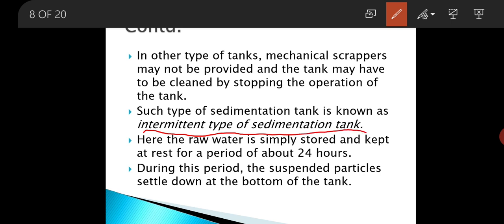One is continuous flow type sedimentation tank, and the second one is intermittent type of sedimentation tank. In continuous type, the sludge is removed continuously or periodically without stopping the working of the tank. But in the case of intermittent type, the raw water is simply stored and kept at rest for a certain period. During this rest period, the suspended particles settle down at the bottom of the tank and the clear water is taken out.